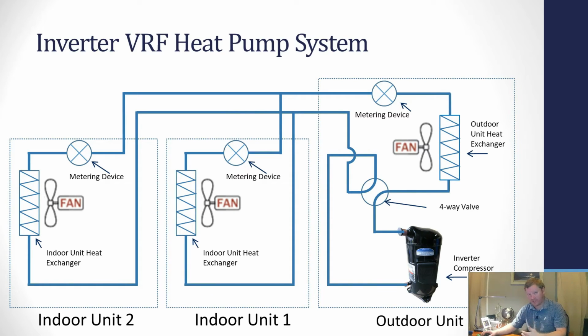So now if my set point is 70, the unit is going to try to heat or cool to 70. We have additional controls that allow us to have what's called a deadband, a thermo on-off deadband of 1 degree in many cases. Now, this is going to vary slightly from brand to brand, but most of your VRF brands give you the ability to have a 1 degree thermo on-off deadband. And what that means basically is if indoor unit 1 has a 70 degree set point, when that temperature at your thermostat drops to 69, just 1 degree below set point, it's going to call for heat.